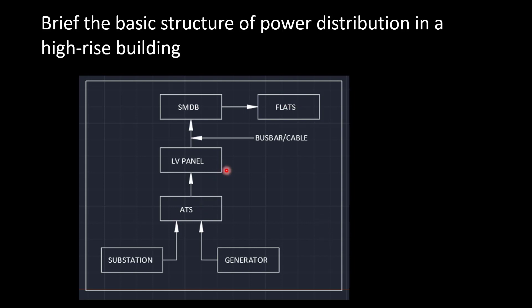From substation and generator, the power flows through the LV panel via ATS, then LV panel to sub-main distribution board (SMDB), and from SMDB to flat DBs or final distribution boards. This is a block diagram of a typical residential high-rise building. The ATS and LV panel will be situated in the main electrical room or LV room, either in the first basement or on the ground floor. SMDBs will be situated in the respective electrical rooms on different floors, and flat DBs will be placed inside the flat.